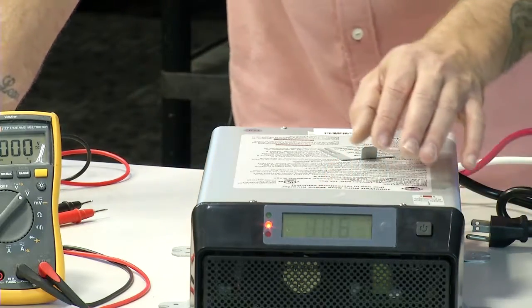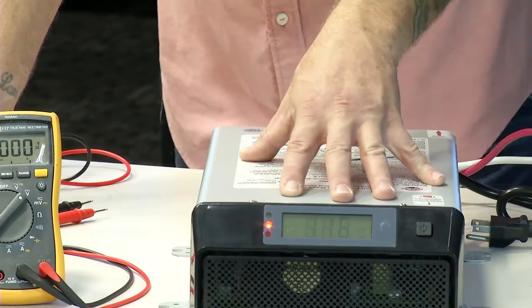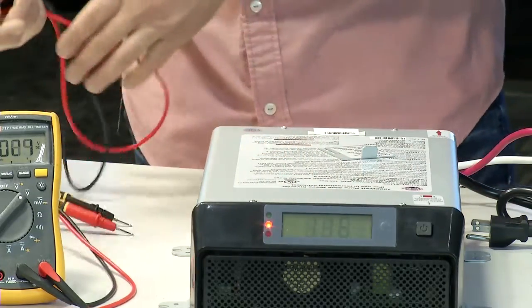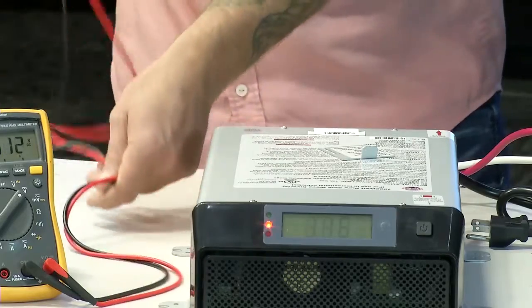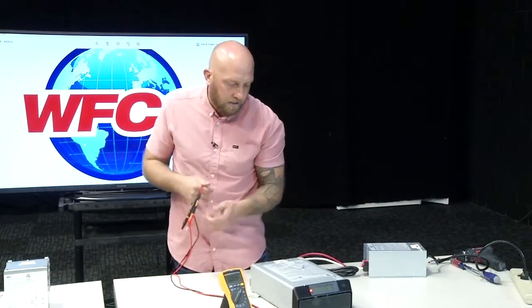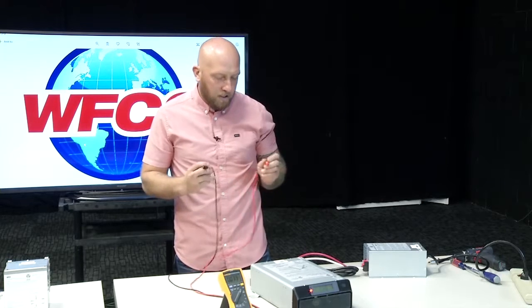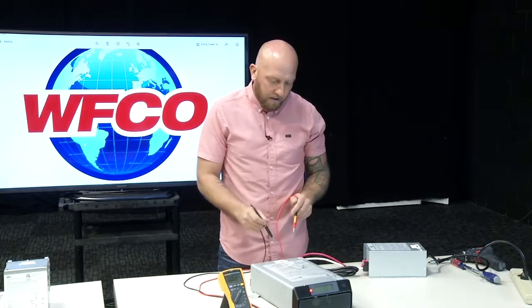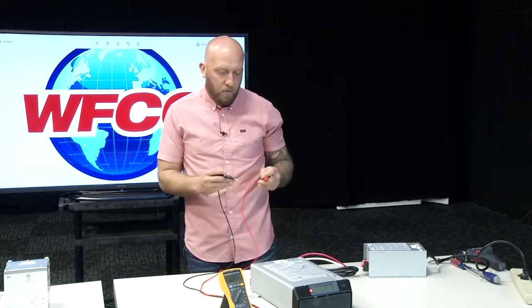So we're back to AC volts. That's what's going to be shown the very first time you turn on the inverter, your 116 AC volts. That's what it's putting out. Just because the screen says it's putting out 116 AC volts, you want to check at the wires coming out the back of the inverter that I showed you, your black, white, and green wire.